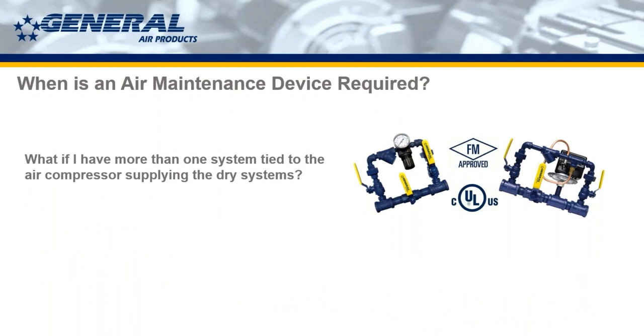Another question that comes up very commonly with air maintenance devices is, what if I have more than one system tied to the air compressor? If you have one compressor and 3, 4, 5, 6 dry systems, I'll just put a word in here: there is nothing in the standard that says you can't tie one air compressor to 20 systems. The standard doesn't include good sense. It just tells you what you should and shouldn't do. Based on feedback and everything, we're trying to get some changes made in this regard, because you really should not set 20 systems on one air compressor. You're really putting a lot of work onto that air compressor, but not only that, you're going to kill it very early. Compressors don't really last by years, they last by hours, run hours.